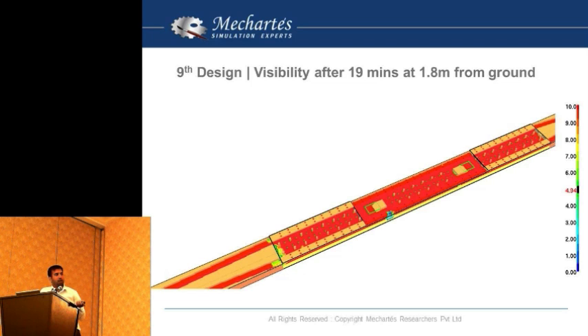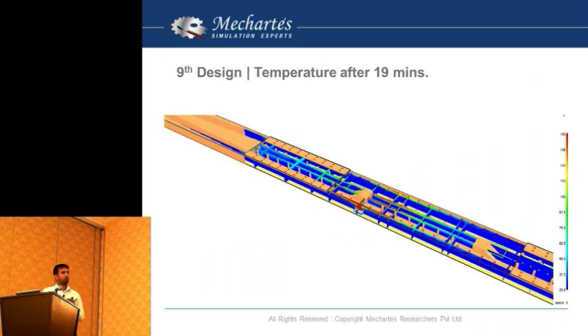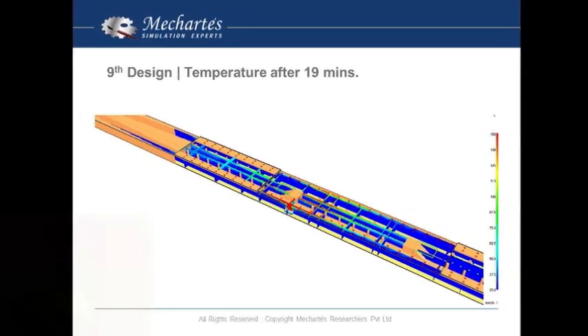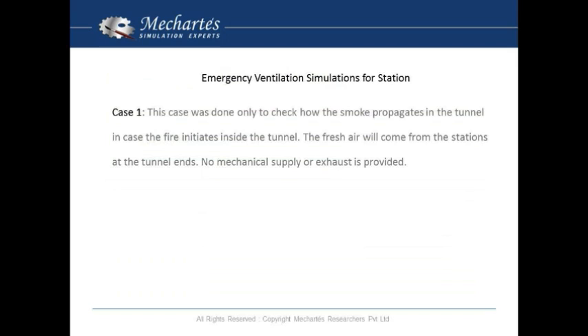After 19 minutes, when the fire is at peak, the visibility at 1.8 meters from the ground showed most of the area has visibility of more than 10 meters. Only in the corner area of the platform and near the fire was visibility less. The two fire exits had good visibility so people could run away. High temperatures were close to the ceiling, and in the occupied zone the temperature was not unfavorable.